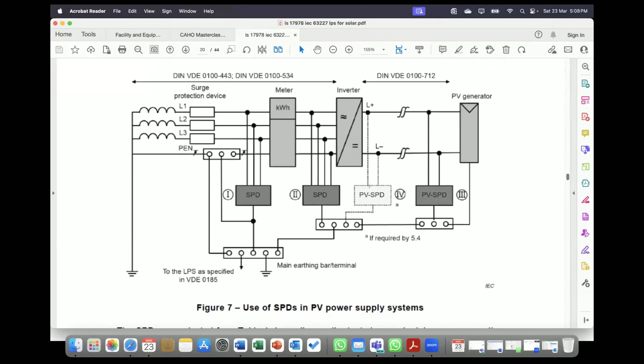Then at the inverter side, there is one more equipotential bonding bar, which then goes to the main earthing terminal. This is the correct way of earthing for achieving safety and reliability in a solar PV installation.